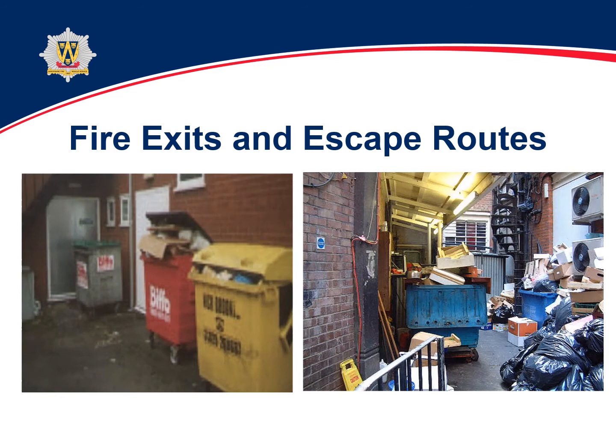If you look at the picture on the left, you can see that someone has pushed a wheelie bin up against the fire exit. So although you may have made sure that the route inside is clear, when you get to that door it may not open because it's blocked. Then on the right, the escape route has lots of storage of combustible materials. So again, that escape route is compromised. So it's always important to do these checks inside as well as outside.